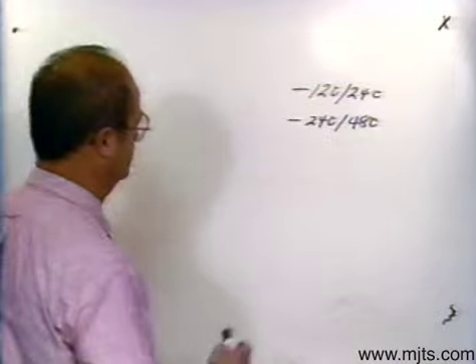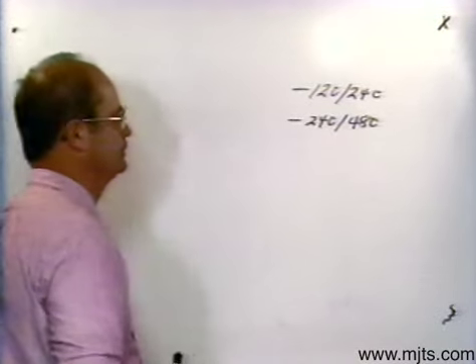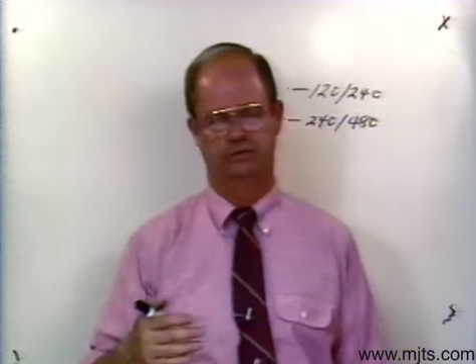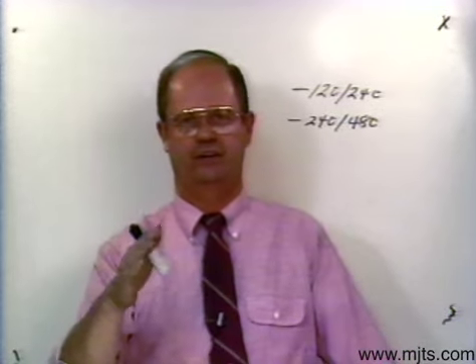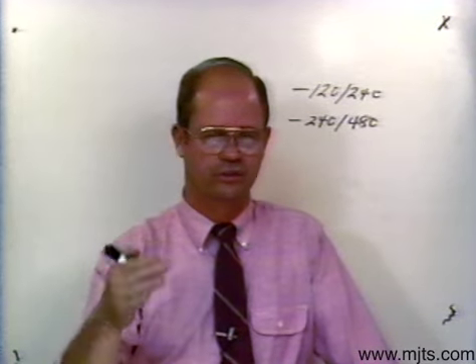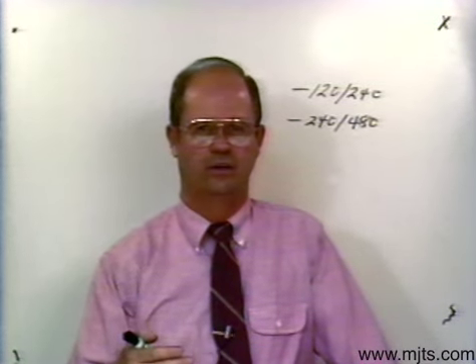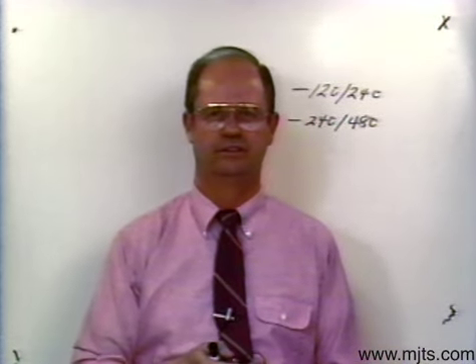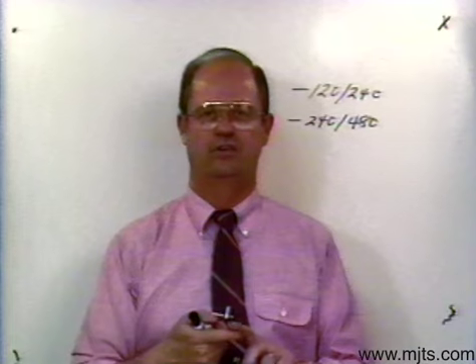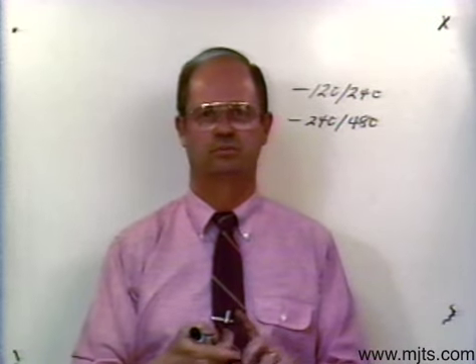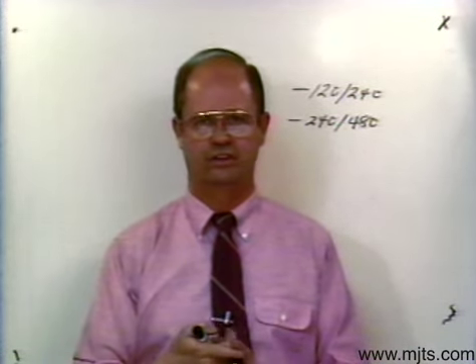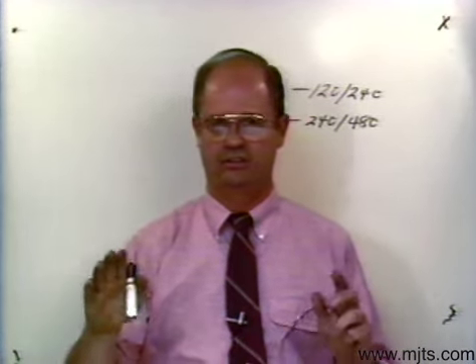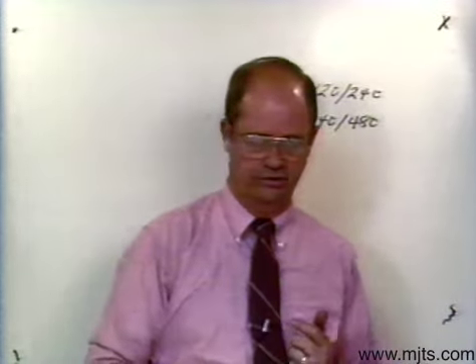Written in this way, I will know the design of that transformer for the low side. When it's written like this, it means that transformer is capable of connecting for either the lower value or both, depending on whether I series or parallel the internal connections. Some are going to have external connections — I'll get into the four-bushing in just a little bit.